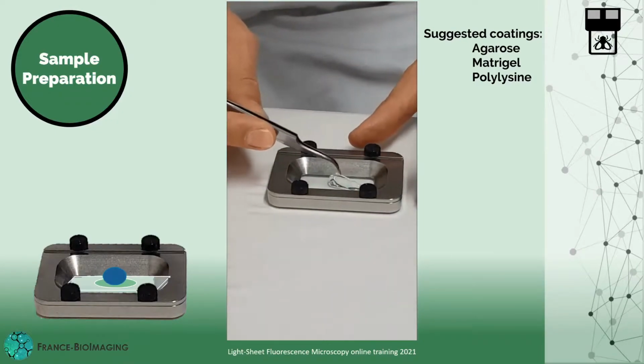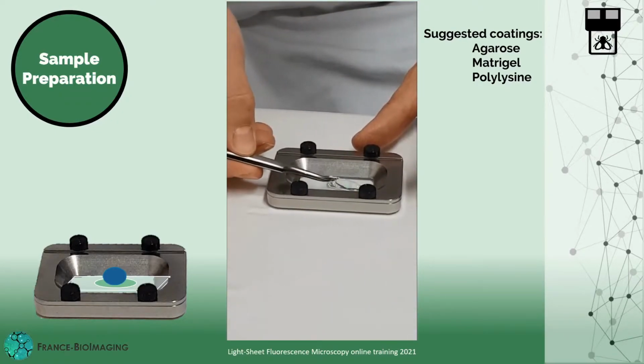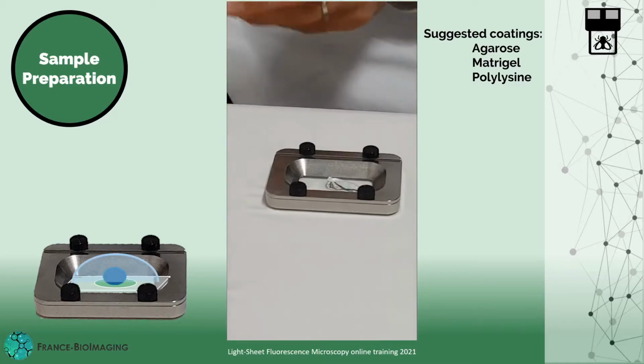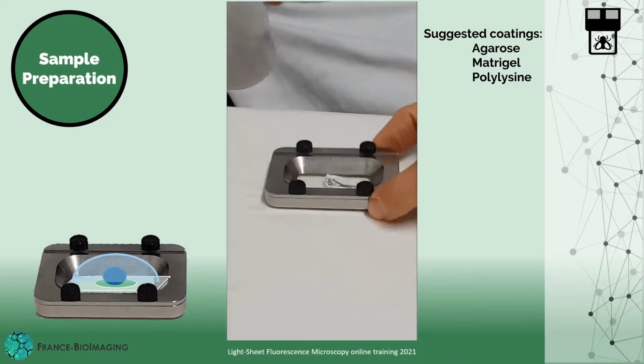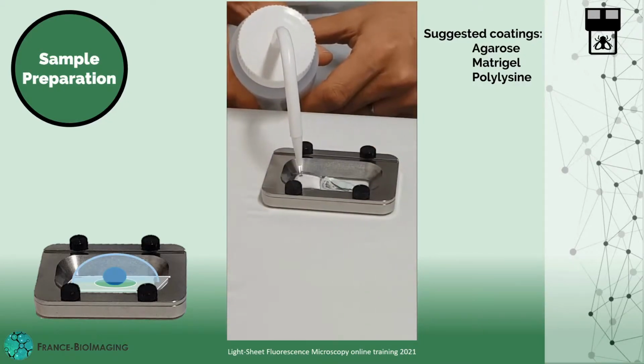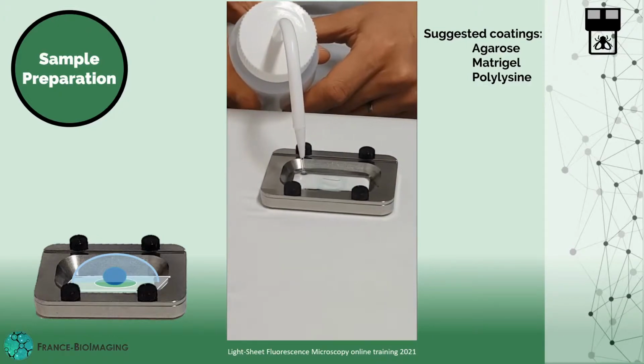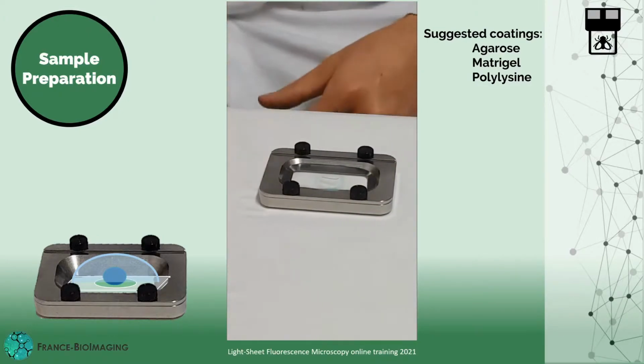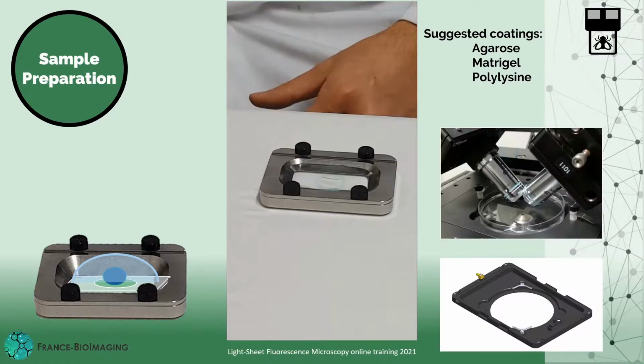Given the mechanical dimensions of the chamber, particular care needs to be taken to position it as close to the center of the slide as possible. This will prevent the reduction of the observation field due to the objective bumping into the side of the chamber. In order to increase the freedom of movement of the chamber, other large inserts may be used, such as an 85 mm diameter Petri dish.